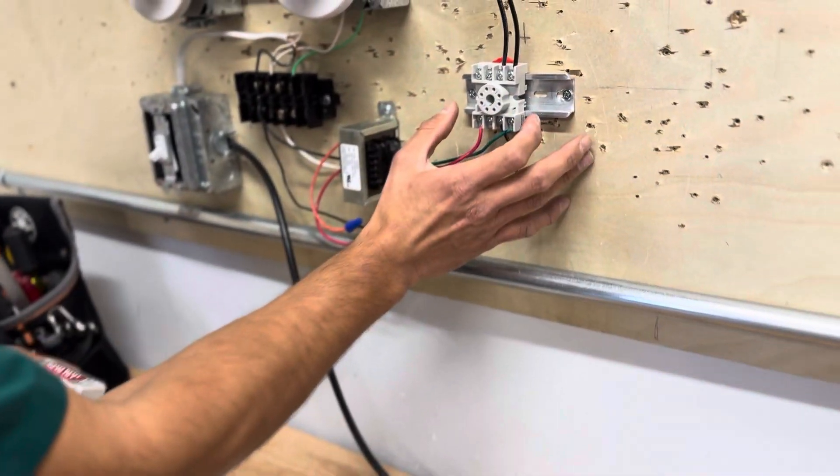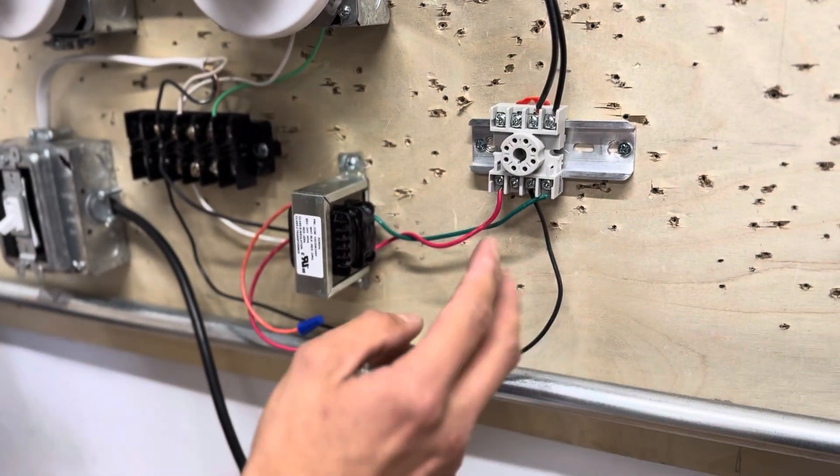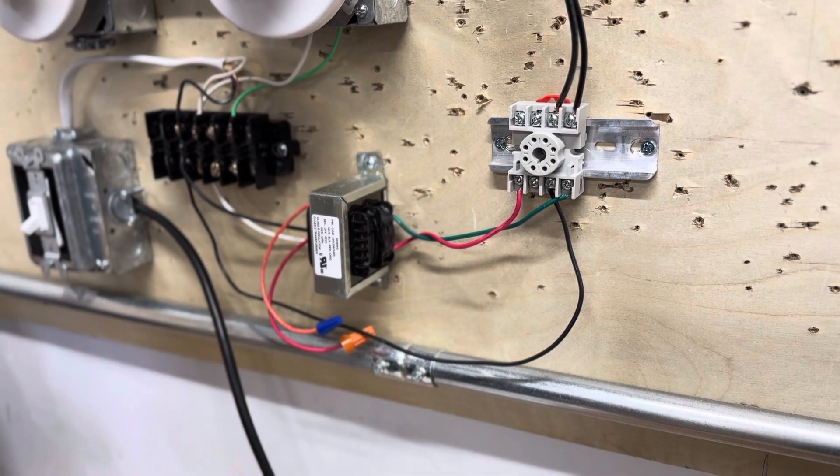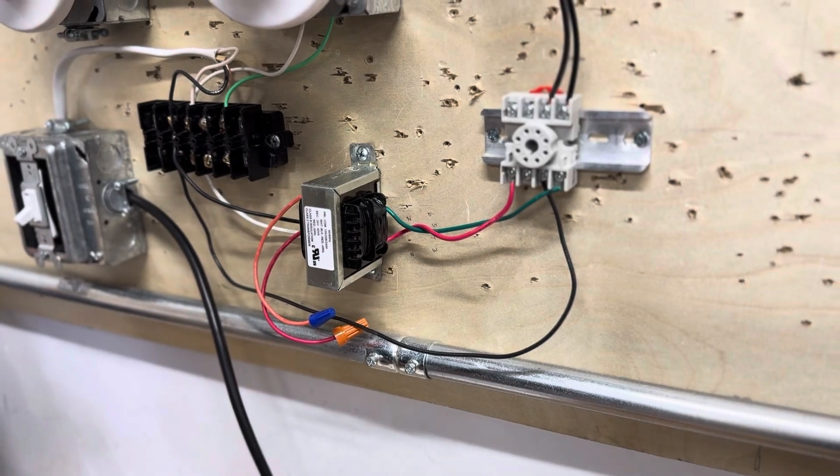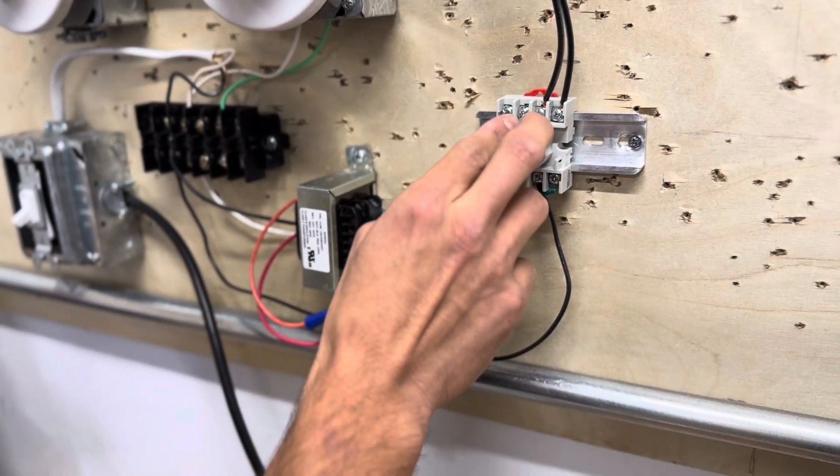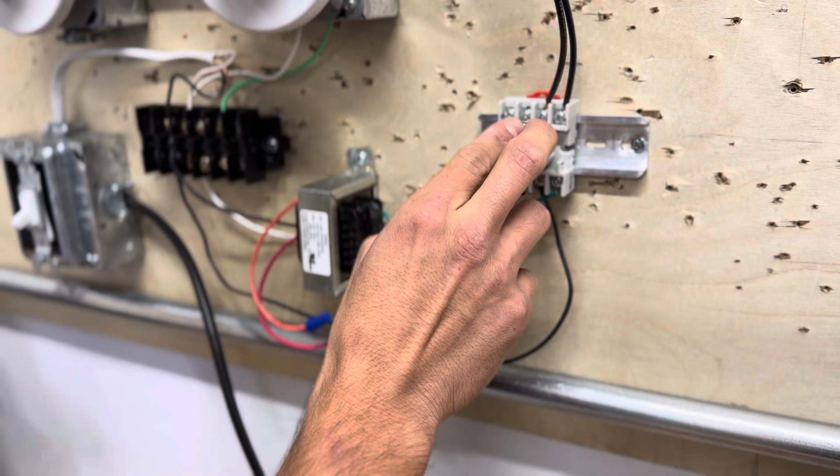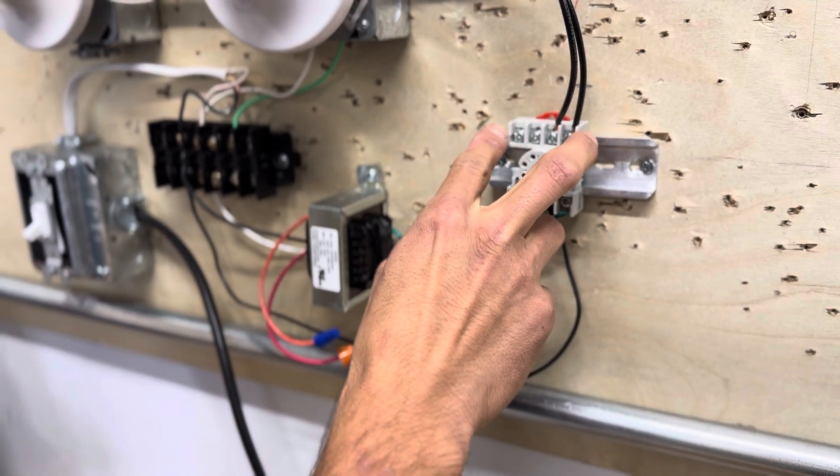So now let's go over the different pin outs here. This is your 8-pin base. Pins 2 and 7 are for the coil, and there are two sets of normally open and normally closed. Now the two in the middle up here are normally closed contacts. The two on the outer are normally open.